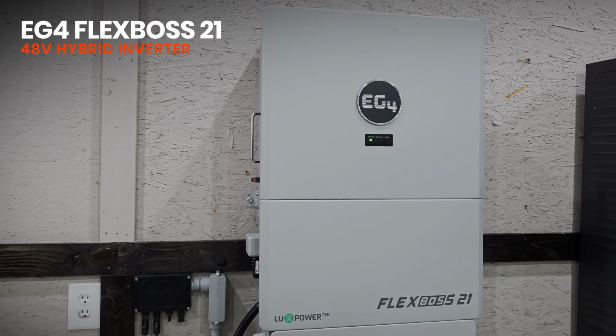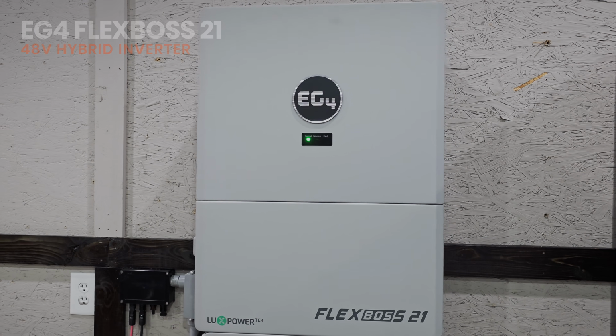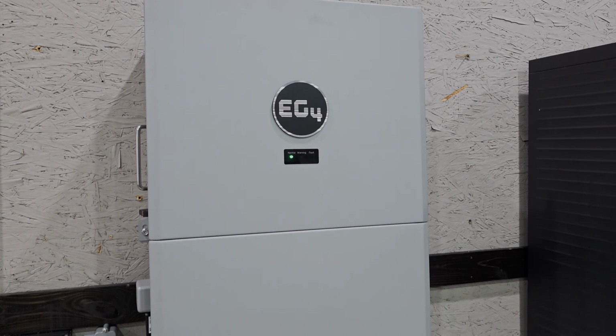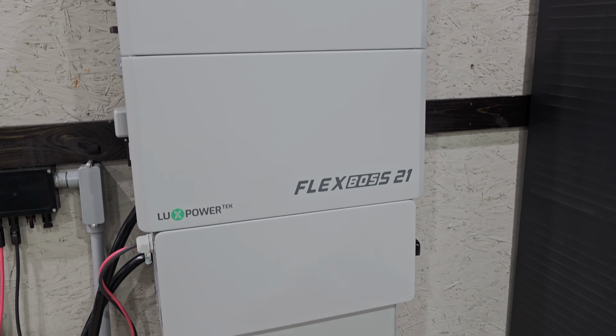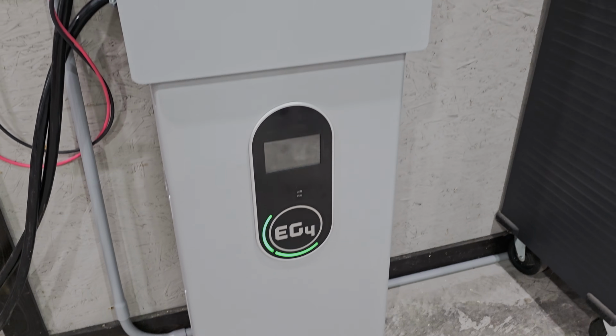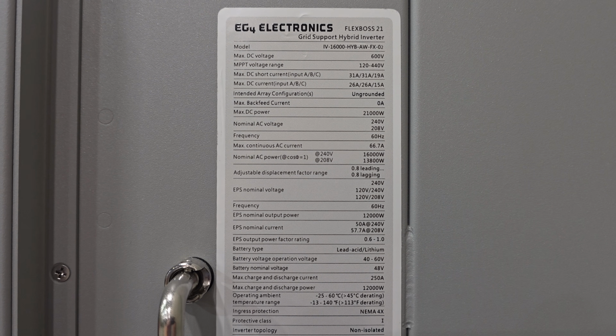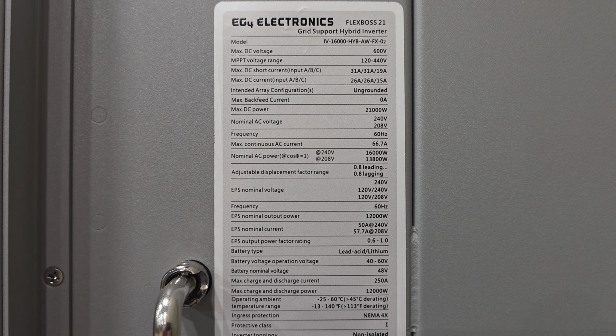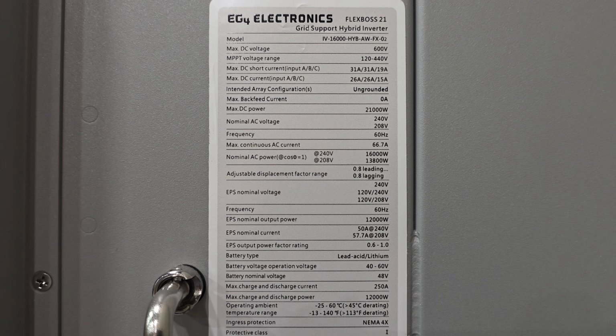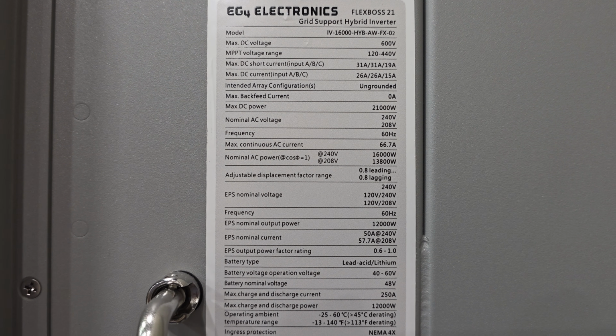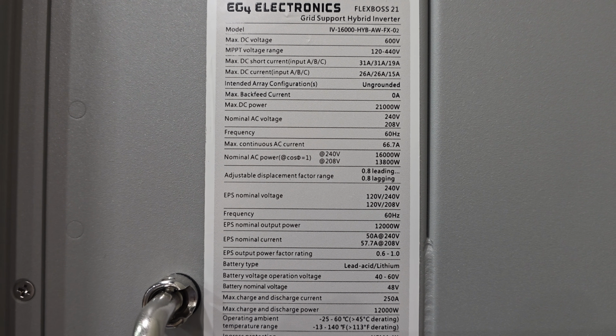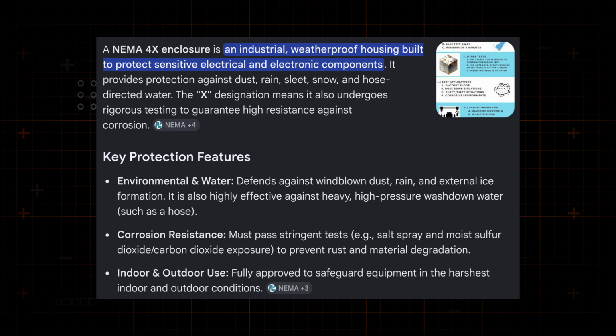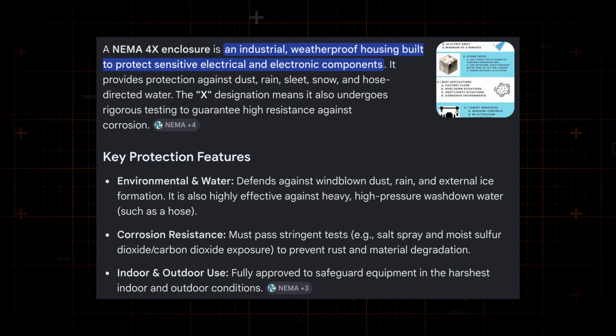This is a 48 volt hybrid inverter designed for backup power, solar input, battery charging, off-grid operation, and grid interaction setups. And right out of the gate, EG4 is giving you some pretty serious specs. You get up to 16 kilowatts of continuous output when solar and battery are working together, 21 kilowatts of PV input, and you could parallel up to 16 units. It has a NEMA 4X outdoor rating enclosure, and you get a 10-year warranty.